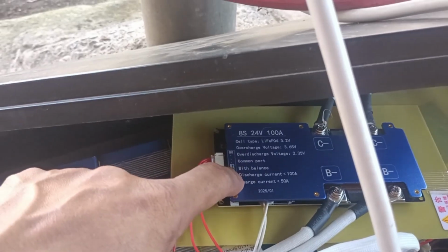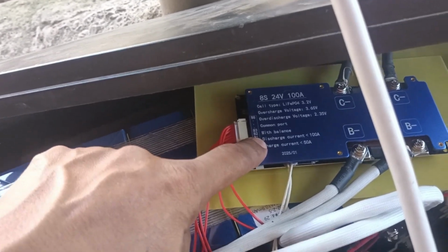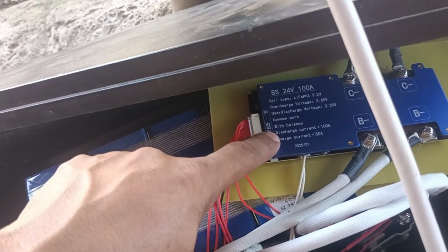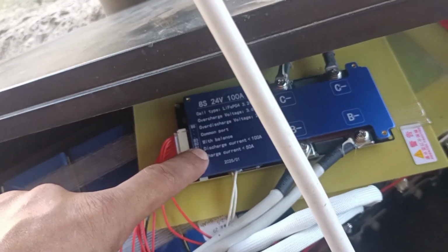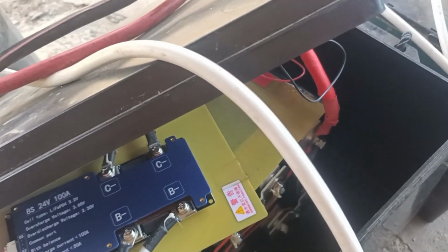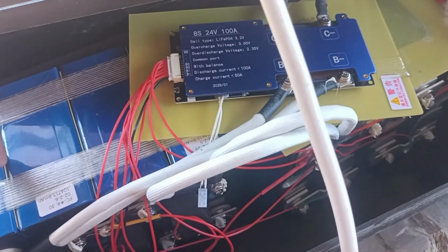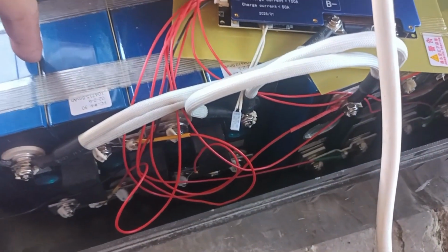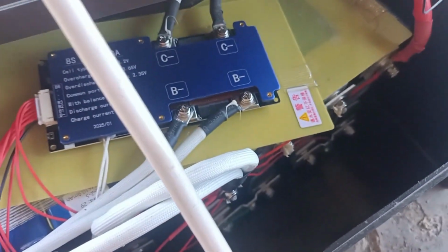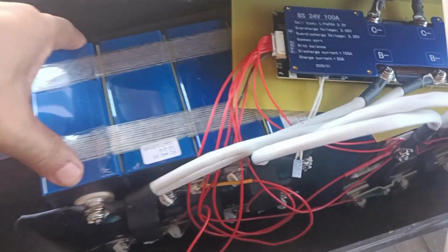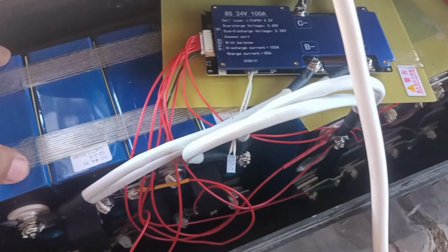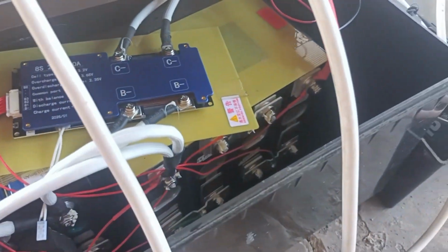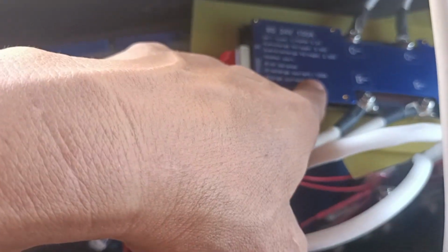So that's where the control is. So the BMS is controlling it, because it's not precise, 3.47, and then some are 3.5. Not a lot of 3.5. The majority of voltages are at 3.47. So I'll do some math. So I did some quick calculation. 3.47 times 8 is 27.7 volts. That's what it is. I think it's charged.